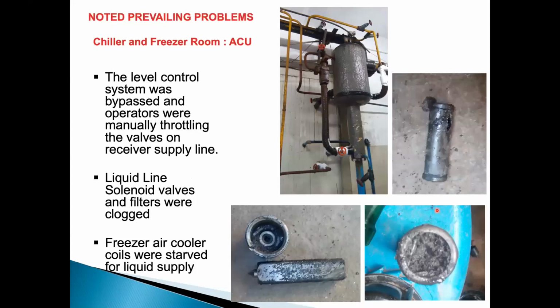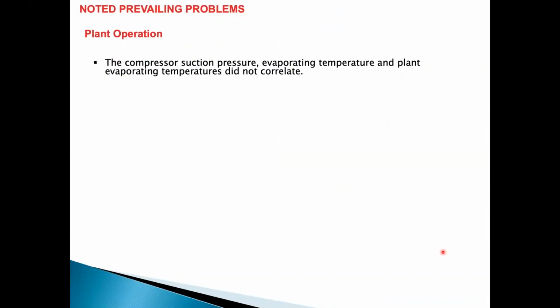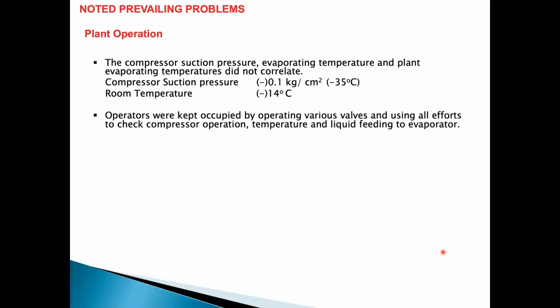The plant was provided with a level controller system, but it was not working and was totally in manual operation. The filters were choked and damaged, with heavy sludge and rust in them. Because of this, all the coils were always starving of liquid, not getting sufficient supply. The compressor suction pressure and evaporating temperature were nothing like the intended operation. Compressor suction pressure was minus 0.1 kg per centimeter square, which corresponds to minus 35. So in the room you should get at least minus 30 degrees centigrade, but they were able to get only minus 14.